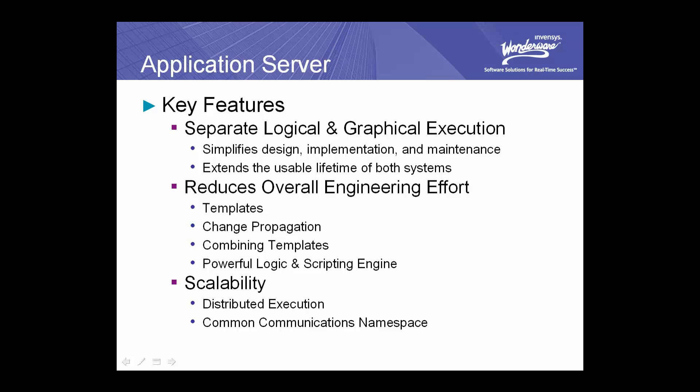Finally, we'll wrap up our review of this foundation product by looking at its scalability. When you create instances from your templates, you also tell the system where these instances will be running or executing — it might be an HMI node or a server without any HMI at all. You decide where those elements will be executing their data acquisition, scripting routines, and historization logic. If one machine gets overloaded, you simply drag and drop the objects to another node. The amazing thing is that this doesn't impact any of the other components on the system. Application Server utilizes a common communication namespace — meaning you don't need to know where the data is. It can go find it. So if I move BrewKettle 100 from one PC to another, I don't have to update my HMI applications — they automatically know where to look.